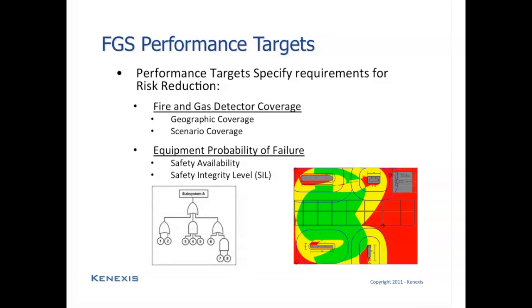And the outcome of the scenario coverage will essentially be a map of where the risk scenarios are occurring, a geographic risk profile, for those of you that are familiar with quantitative risk analysis, and also a mitigated geographic risk profile where the scenarios that have been detected are removed from the geographic risk. And also, there will be a tabular calculation of the fraction of the scenarios that are not detected, the fraction detected by only one detector, and the fraction detected by two or more detectors.